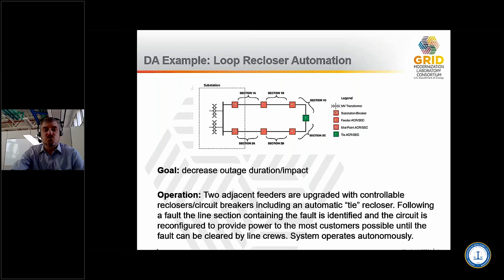The idea would be that at the end of the day, you only have section 2A that's actually outaged, because that's where the actual fault happened. And of course, the truck crew would run out there, clear that fault, fix whatever's wrong, that sort of stuff, and then eventually the system would be back up and running. But during that actual fixing period of time, at least 2/3 of the customers on that lower feeder would not have an outage. The system operates autonomously. It has a single function, right? It's really meant to decrease outage impact and duration, and keep most customers online. And this equipment communicates with itself. And to be honest, most of these are implemented using a proprietary system, if you will, that you buy from a vendor, and that's what its single function is. Let's go to the next slide, please.